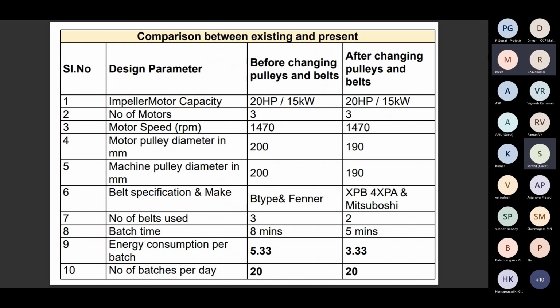So this is the existing and the present. Before changing the pulleys and belt, it was a 20 HP, 15 kilowatt motor. The number of motors is 3. This particular example I am discussing is with one shot blast machine only. The motor speed is 1470 RPM. The motor is the same because we are not changing it; only the pulley and the belt were changed.